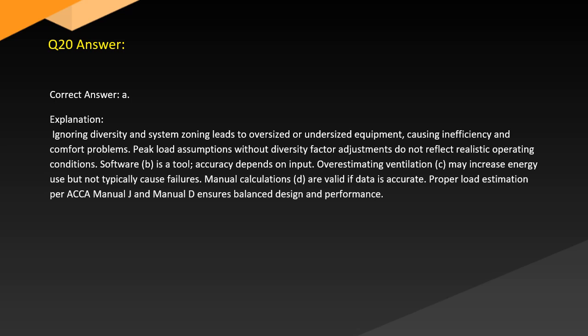Ignoring diversity and system zoning leads to oversized or undersized equipment, causing inefficiency and comfort problems. Peak load assumptions without diversity factor adjustments do not reflect realistic operating conditions. Software, B, is a tool, and accuracy depends on input. Overestimating ventilation, C, may increase energy use but not typically cause failures. Manual calculations, D, are valid if data is accurate. Proper load estimation per ACCA Manual J and Manual D ensures balanced design and performance.